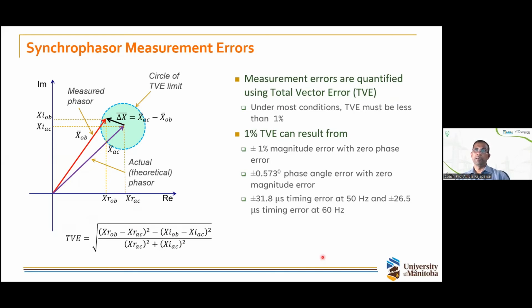Quite often there is a limit for the TVE, the total vector error, and this limit is typically 1%. With this 1% limit, you can define a circle like this around the end of the actual vector. This is a little bit enlarged, but if you draw 1% of this vector, then if your measured vector lies at any point within this circle, it is accurate enough. But if it goes outside, then the accuracy is not within the defined limit.